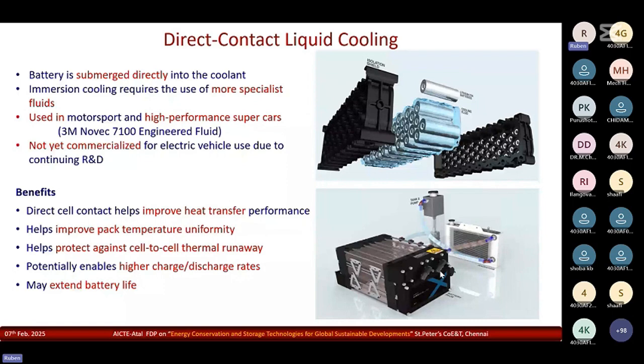Between the cells there will be a gap. The fluid we pass in will flow through the interstitial spaces between the batteries, and that's going to avoid or protect against propagation of the flame. As you saw in the video I showed you, there was propagation of flame when one cell started firing and the nearby cell also caught fire. This can probably be protected against, avoided, or slowed down by having these kinds of direct liquid cooling systems.